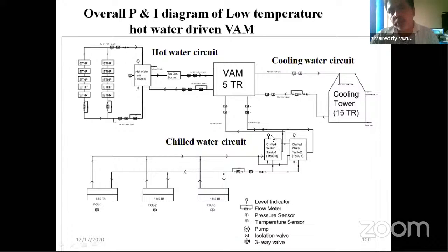What is the main purpose of the cold water? The requirement was, once the product is harvested, 2 tons, 3 tons of product come to the cold storage at a time. At that time, sudden cooling is required. We can't wait to run the VAM and then produce the cooling effect. Immediately we want to cool. So ready availability of a chiller facility is required. That's why we maintained a 3000 liters chiller facility.